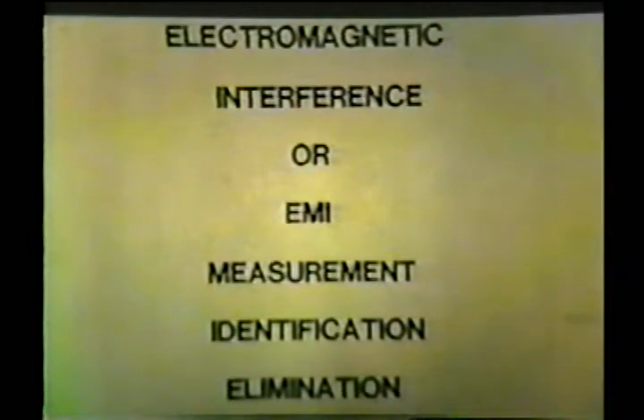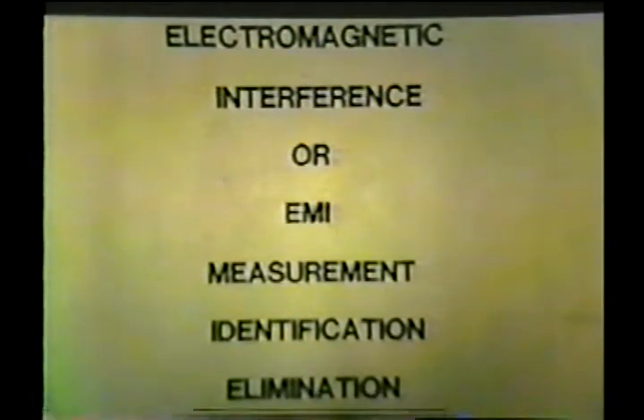Even though modern machines are usually well designed and operated far below the manufacturer's design limits, failures can occur, either in the slot section or in the end windings, depending on the particular failure mode that's involved. In particular, several types of faults can be identified through measuring them by monitoring the radio frequency current at the neutral. In particular, we'll be talking about electromagnetic interference, or EMI, its measurement, its identification, and if considered serious enough, the elimination of EMI through maintenance procedures.